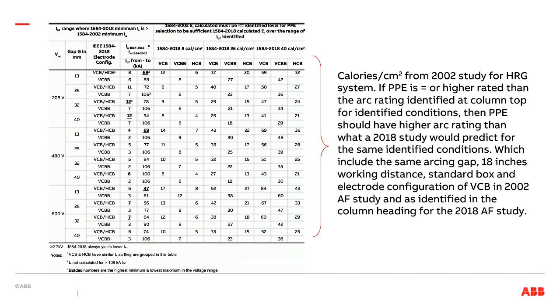And now you can essentially use your 2002 arc flash study to decide whether your task is exposing your worker to more energy than the available or previously selected PPE, and whether you can move forward or do something different. This should be a conservative method. It's not a complete arc flash study and should not be considered to replace an arc flash study, because this is conservative. And in fact, there are many situations here where you are still using more PPE than you need. But there should not be any situation here where you will have less PPE than you need. And this is based on the premise that wearing more PPE than you actually need may be undesirable.